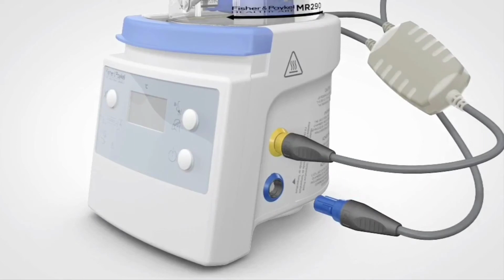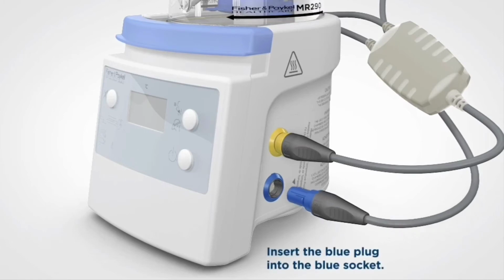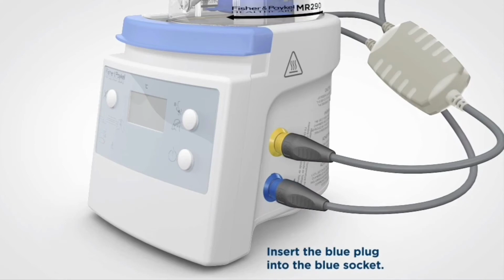Next, let's connect the temperature and flow probe. This adapter has a blue plug and is used to measure the temperature and flow of gas at the chamber and temperature of gas delivered to the patient. This information helps the humidifier control the chamber output temperature and the breathing circuit temperature to ensure optimal humidity delivery. Connect the blue plug to the blue socket. Again, this socket is keyed, so you may have to turn the plug until it clicks into place.